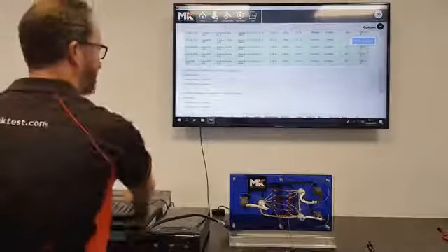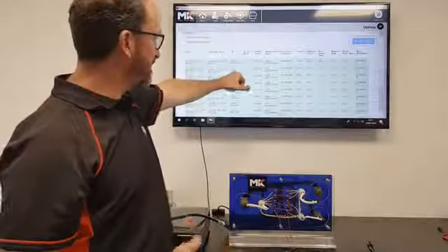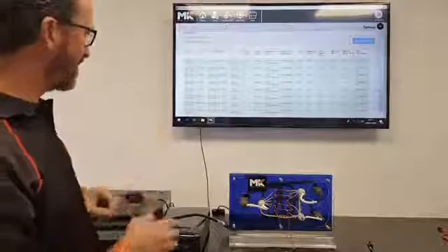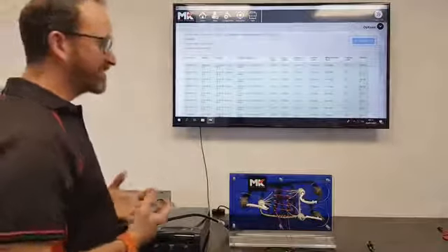The short circuit test, we can see it's run a short circuit test and no failures were found, as expected. High voltage insulation breakdown test or insulation resistance test from each net to all others within that subtest. We've put in 500 volts, we're expecting more than 10 megohms. In fact, we've measured 88, 83, 67 megs between each of those groups, so passed. So as we said earlier, a very clear report, very simple to understand. There's no major skills required to understand green means passed. We're in a good place.